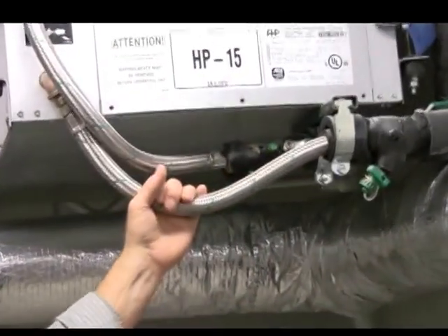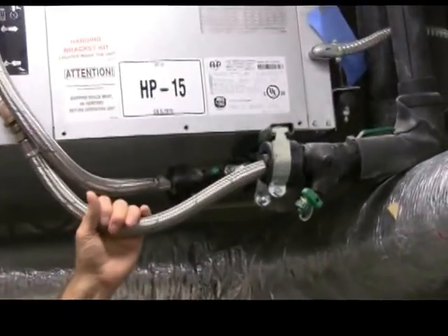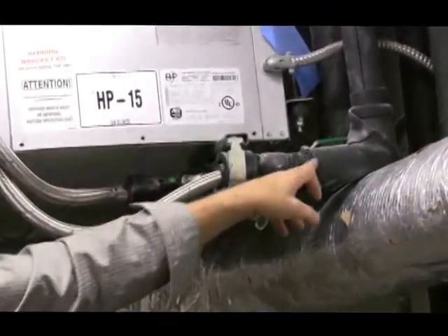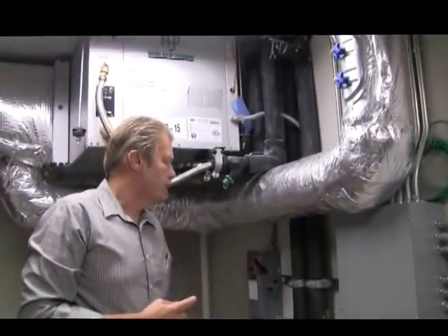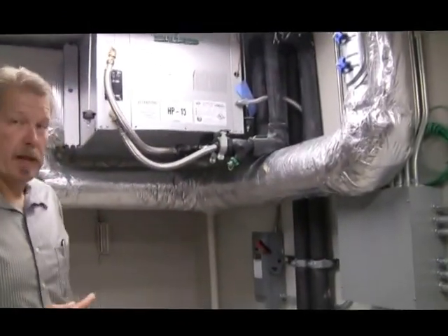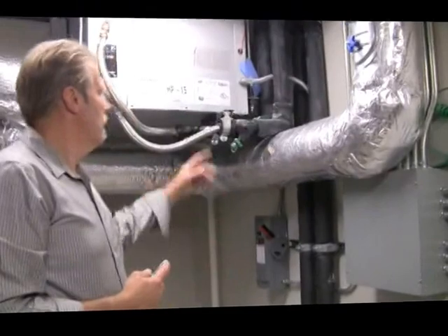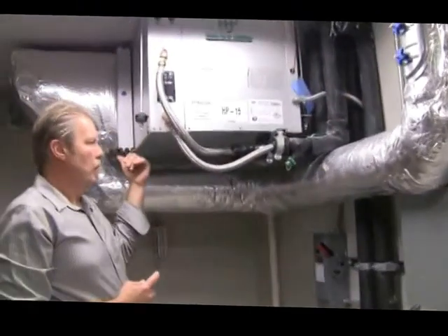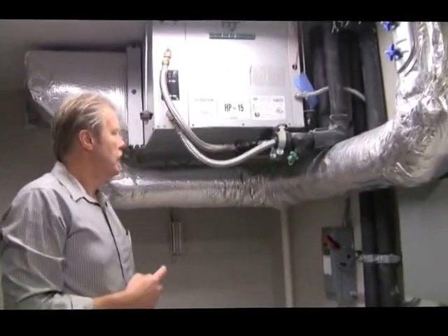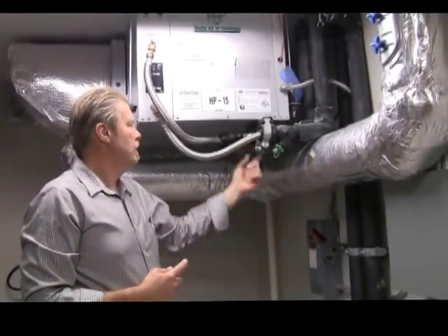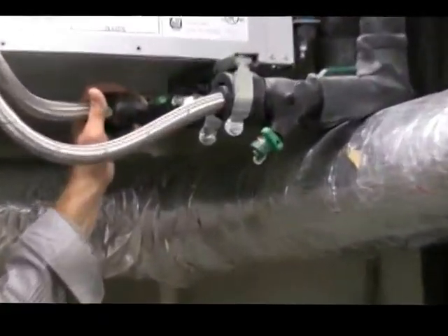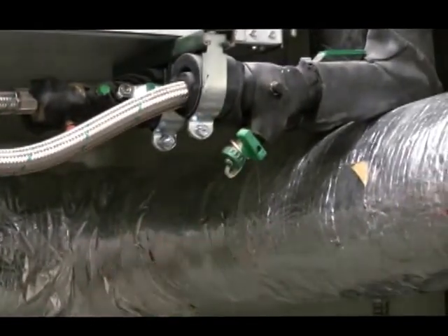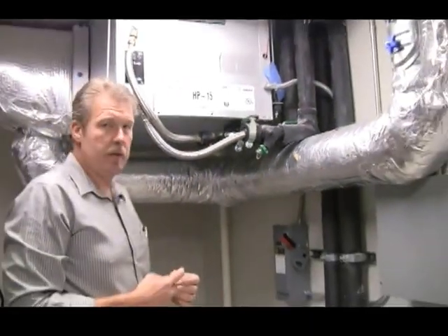These are flexible connection hoses. They absorb any kind of vibration. They're hooked to the geothermal loop, which in these mechanical rooms goes from the main hallway up through here. We tie into a supply and return loop, and the pumps that are in the mechanical room actually provide the flow for us. The fluid flows into the heat pump, and we transfer the heat into it or out of the fluid when it goes back. There are access ports on these units so that we can check temperatures, pressures, and flow. There's really nothing to do as far as maintenance goes for on-site staff.